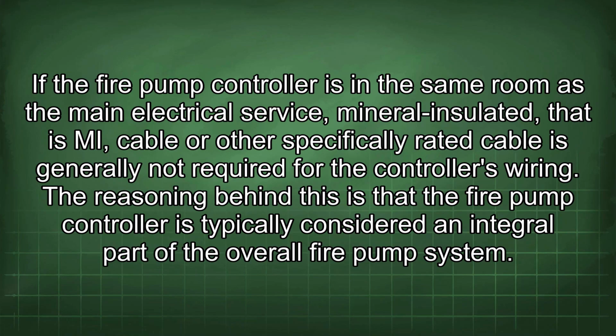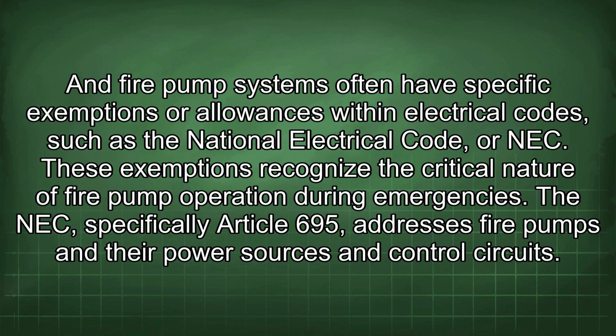If the fire pump controller is in the same room as the main electrical service, mineral insulated, that is MI, cable or other specifically rated cable is generally not required for the controller's wiring. The reasoning behind this is that the fire pump controller is typically considered an integral part of the overall fire pump system, and fire pump systems often have specific exemptions or allowances within electrical codes, such as the National Electrical Code, or NEC. These exemptions recognize the critical nature of fire pump operation during emergencies.